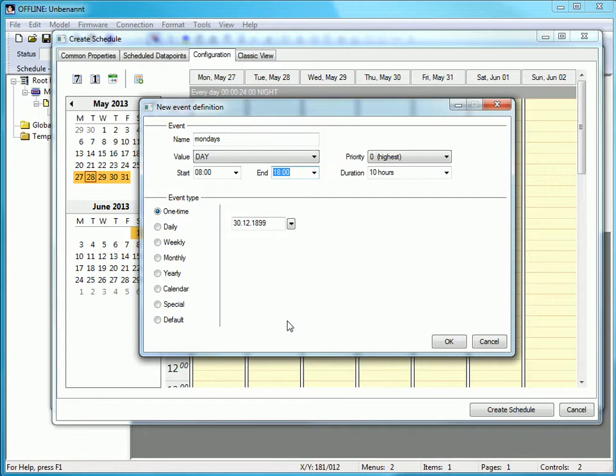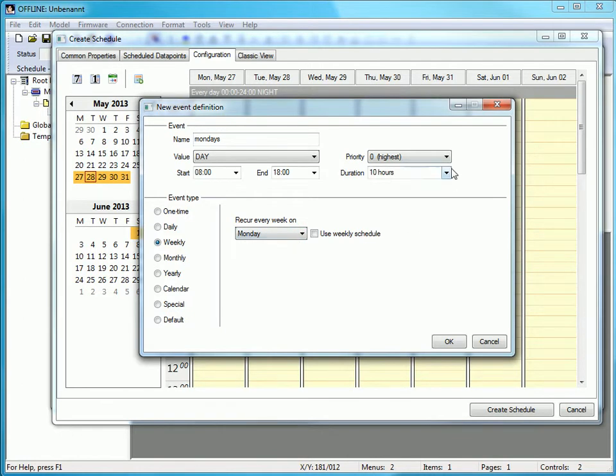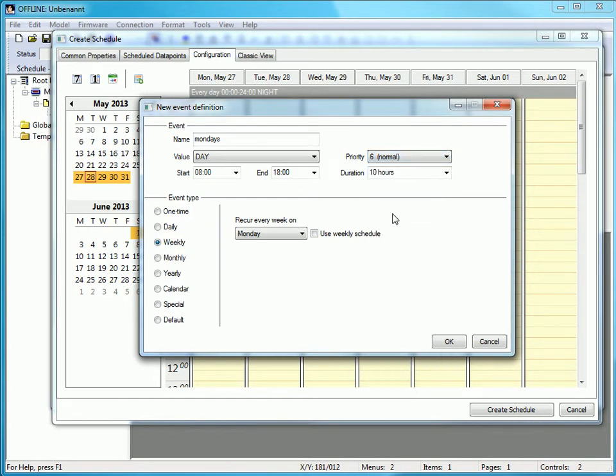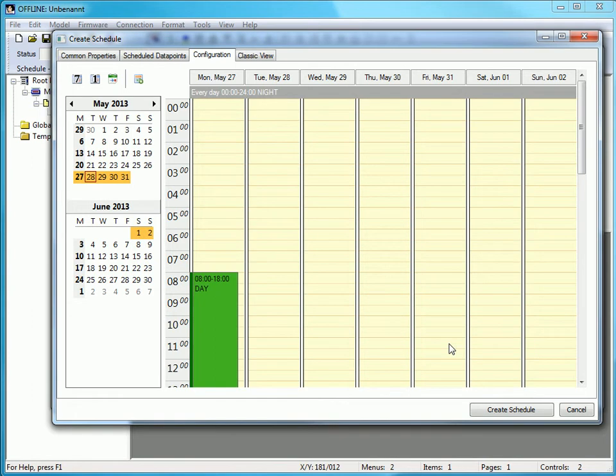You can select from different event types. In this example we choose weekly because the heating should follow this scheduler every Monday. Last but not least you can select a priority: 0 means highest priority and 126 means lowest priority. Finish the action by clicking OK.